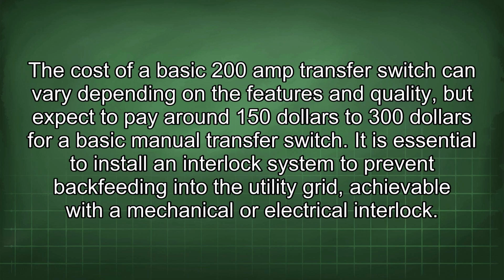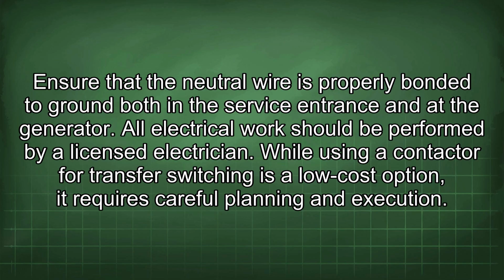The cost of a basic 200 amp transfer switch can vary depending on the features and quality, but expect to pay around $150 to $300 for a basic manual transfer switch. It is essential to install an interlock system to prevent backfeeding into the utility grid, achievable with a mechanical or electrical interlock. Ensure that the neutral wire is properly bonded to ground both in the service entrance and at the generator. All electrical work should be performed by a licensed electrician.